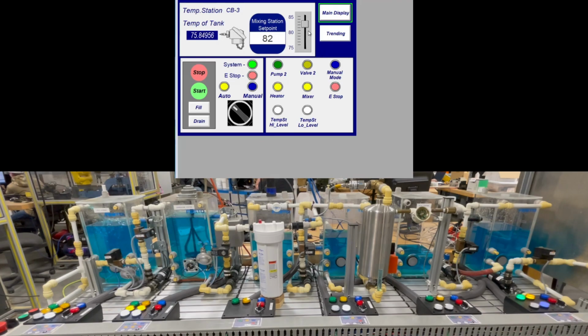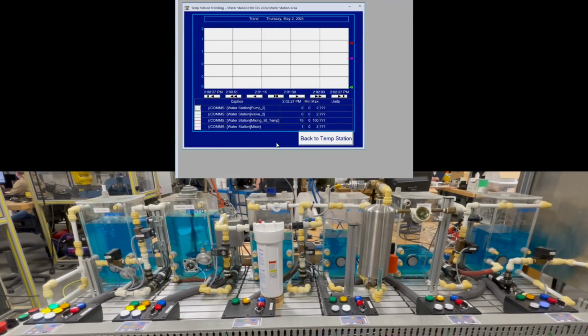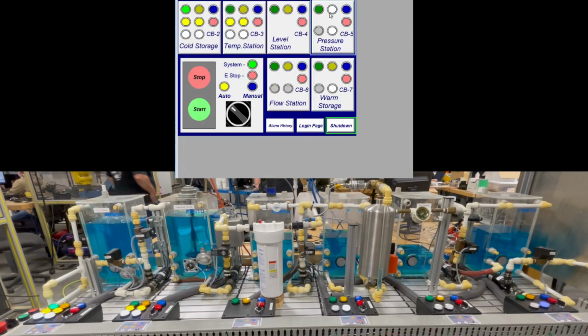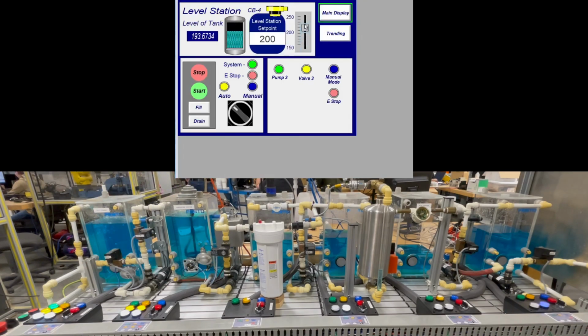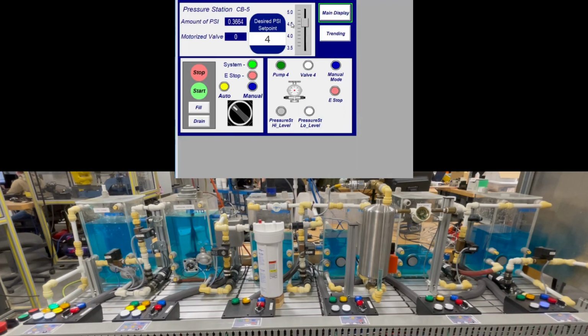As you can see, that mixer and the heater turns on and starts warming up the temperature in that tank. Here is the trending for that temperature station. And then here's the level. You can change the level, and then that pump goes on once I put it below the level because it's already at 200. And then that display thing on the left goes up and down.